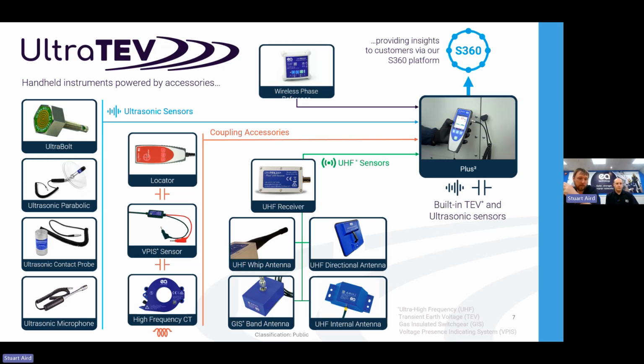We've then added into the UHF range. So there's a UHF expander module, the receiver, which goes into the side of the device. And that increases the input frequency to around about gigahertz and allows us to look in the UHF spectrum, so ultra-high frequency spectrum, at a wider asset base. So in particular, the UHF directional antenna is used now in outdoor compounds, so maybe 132, 400 kV gear, and looking for internal issues with inside insulators. This has the advantage that it ignores corona and very much looks at the damaging PD, the stuff you're interested in. So unlike some of the cameras on the market, it focuses you down to the bits that are really key for your asset management.